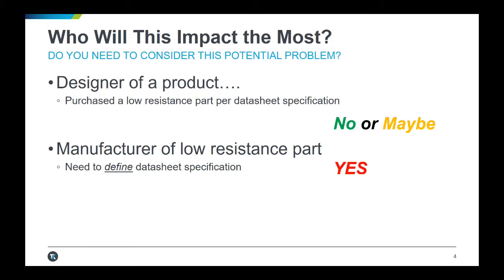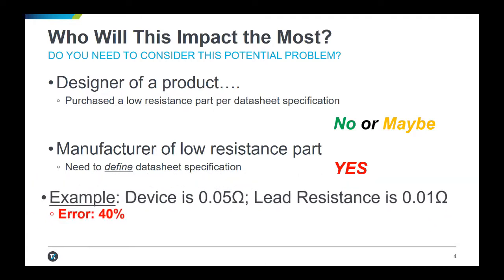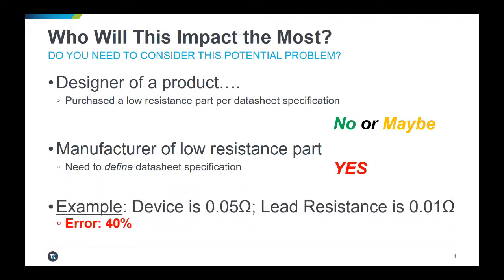Consider the situation where you are making 50 milliohm resistors and your test setup uses leads that are 10 milliohms each. This has the potential to result in 40 percent error in what you are measuring.